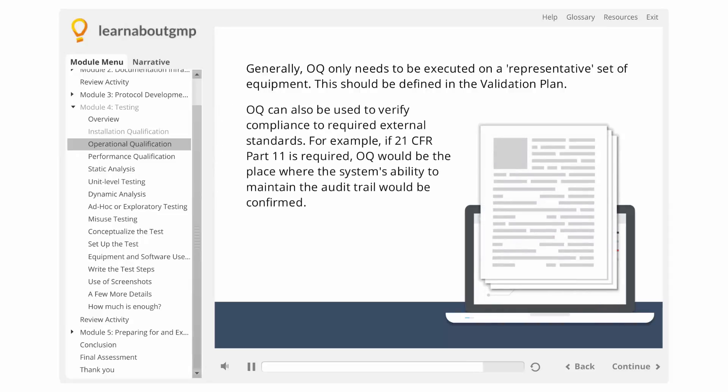OQ can also be used to verify compliance to required external standards. For example, if 21 CFR Part 11 is required, OQ would be the place where the system's ability to maintain the audit trail would be confirmed. The OQ is where the bulk of tracing from requirements to verification occurs.